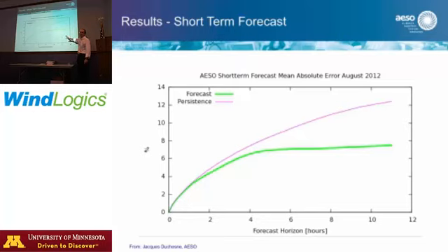And this stays surprisingly flat for the next couple of days. So a one-day or even a two-day forecast is pretty good, but it's in this system-wide error of 6 or 8%, like for an ISO-type system. The pink line definitely is a lot worse once you get out a few hours, but within the first 15 minutes or so, it's very difficult to beat that persistence with a numerical weather model approach because of the reasons I talked about. And the interesting point is the error is really, really low as you approach time zero, because it's not going to change that fast. So this is an important issue we'll talk about, especially when it comes to integrating into markets.